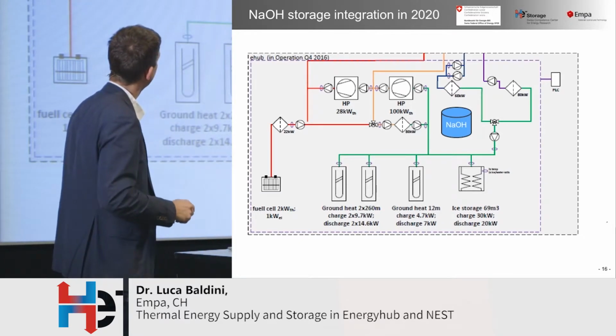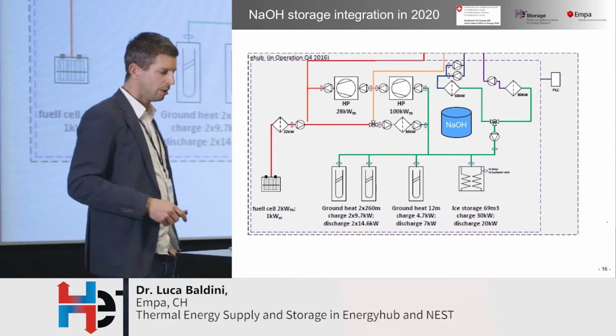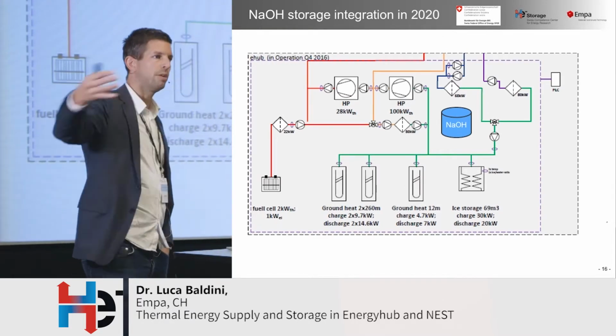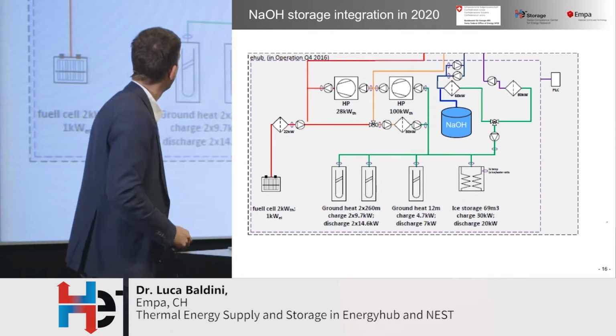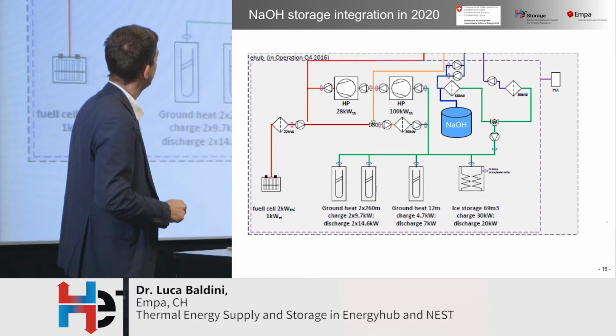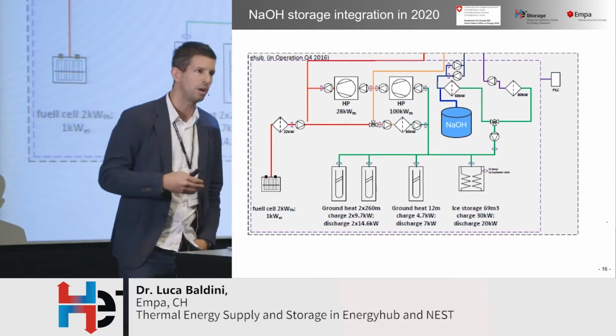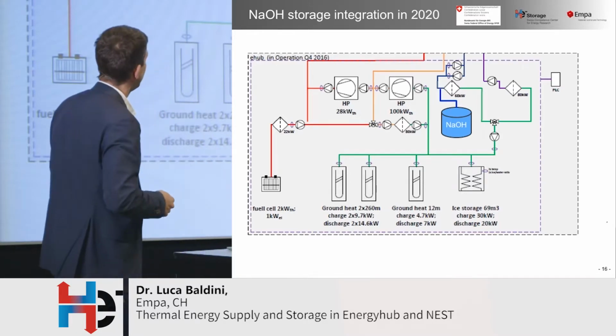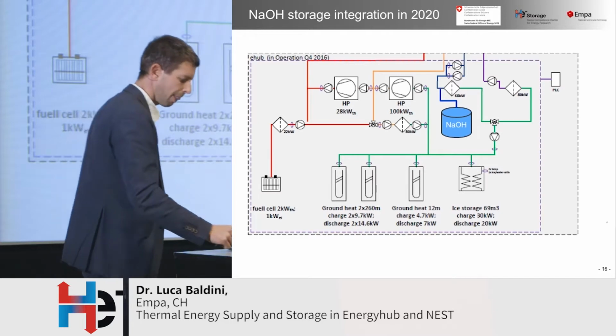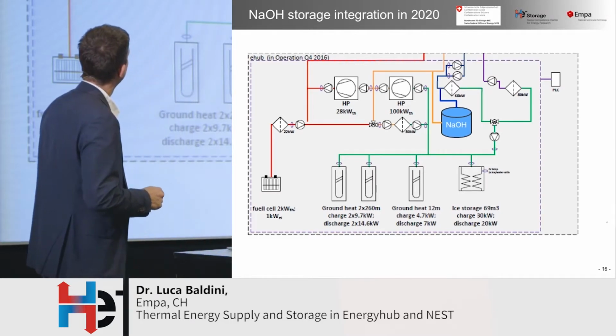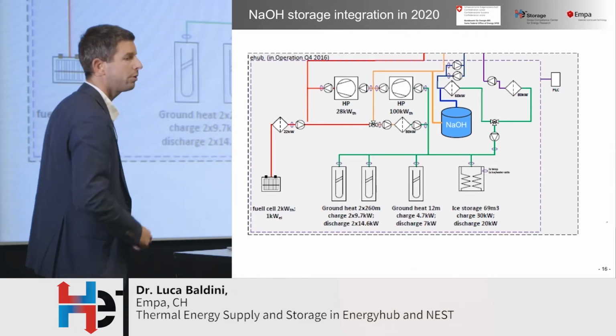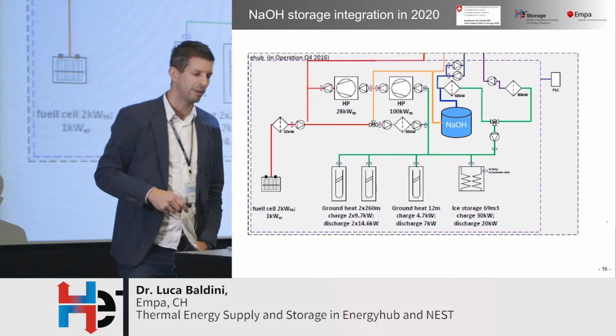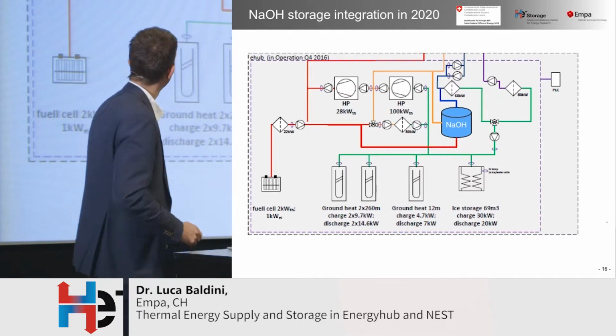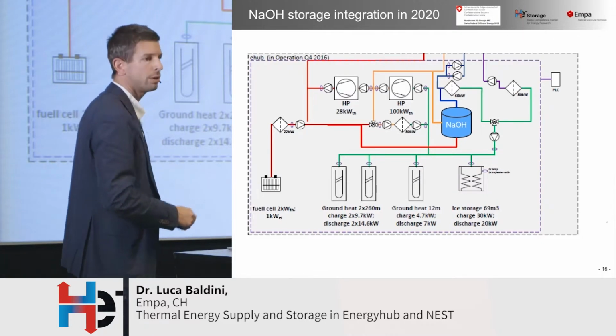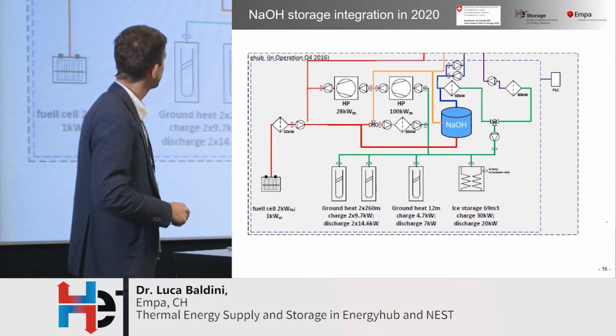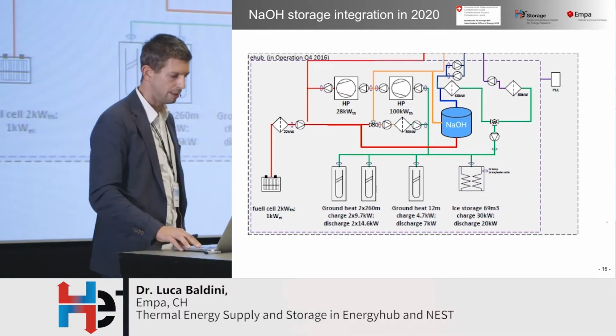With our sorption-based seasonal storage, we are going to place it within the SCCER roadmap, within 2020, in the Energy Hub. We will hook it up to the low temperature grid, which we need to discharge our storage, mimicking in a way a ground heat exchanger. During discharge we bring the heat onto the mid temperature grid at roughly 40 degrees for heating the apartments. And we can use high temperature heat for charging the storage in wintertime, and in summertime with renewable energy at 60 degrees.